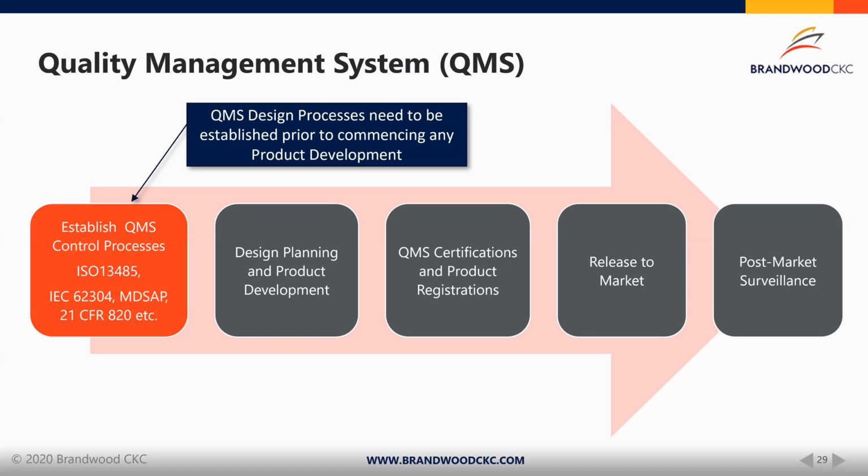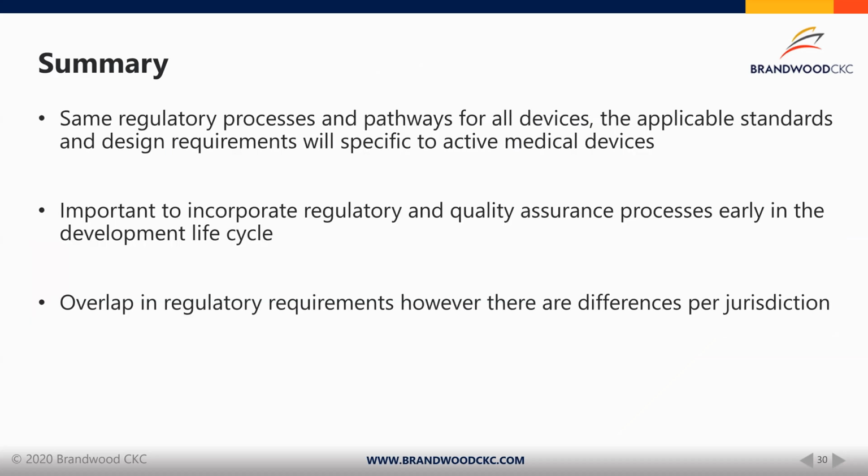So this is just a quick summary. Basically, to summarize, regardless of whether it's an active device, a standard device, or a software, all the regulatory processes, pathways and requirements apply. It's just that there'll be certain things that are specific to whether or not it's an active device, such as that EP12.